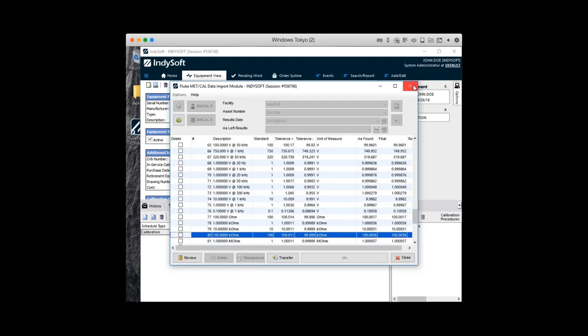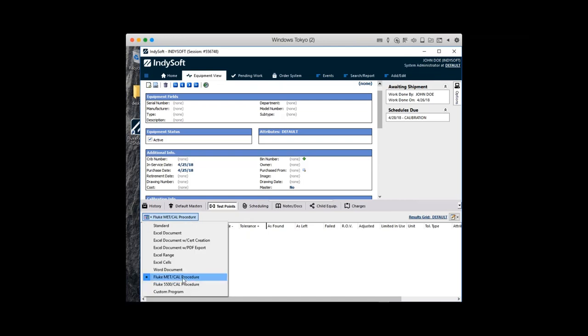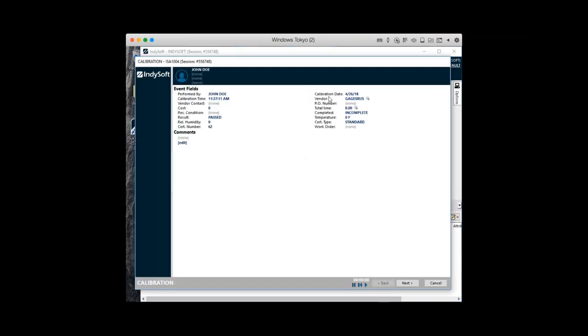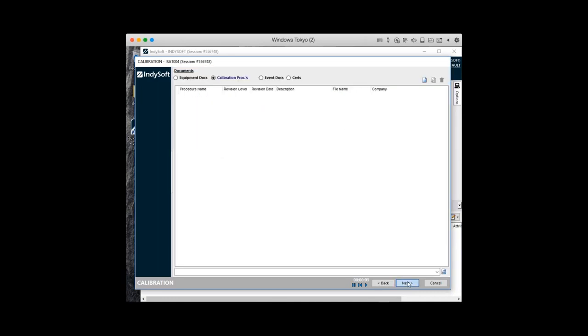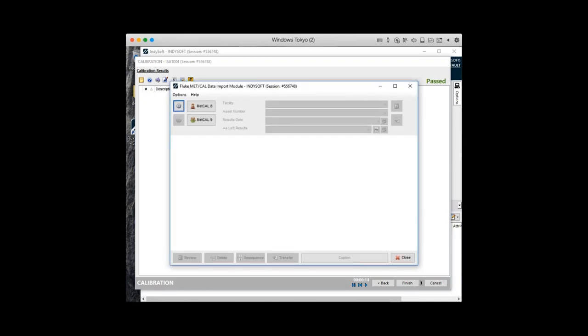To use the importer with an asset, basically what you're going to do is go to the test points tab and select Fluke MetCal procedure as your source for test points. When it's time to work, you simply go into the calibration event as you always do — nothing here has changed — and once you get to the data collection screen you'll click the yellow F icon to launch into the importer. For a technician, we've worked really hard to provide a simple workflow that lets them focus on calibration over configuration. We've flattened the interface to one screen, so there are no wizard steps — everything the technician needs is right here on this one screen. The importer supports both MetCal 8 and MetCal 9; on this system we have both configured, which provides two options.